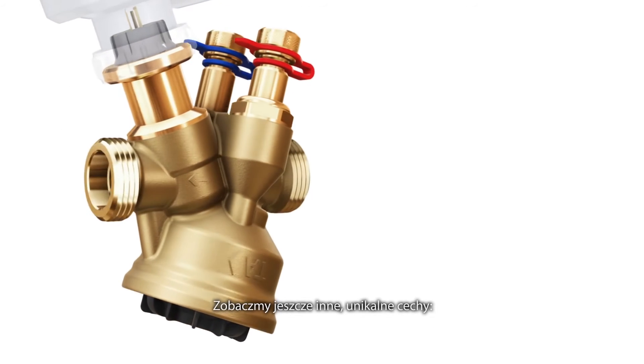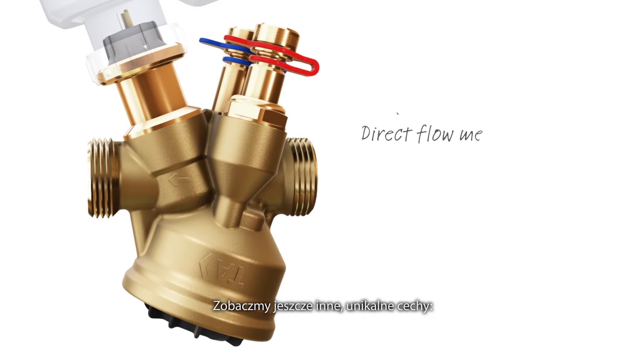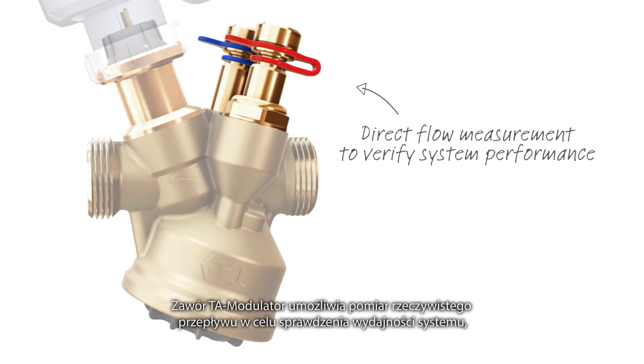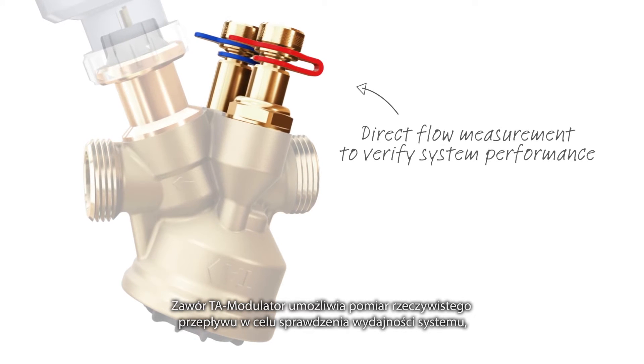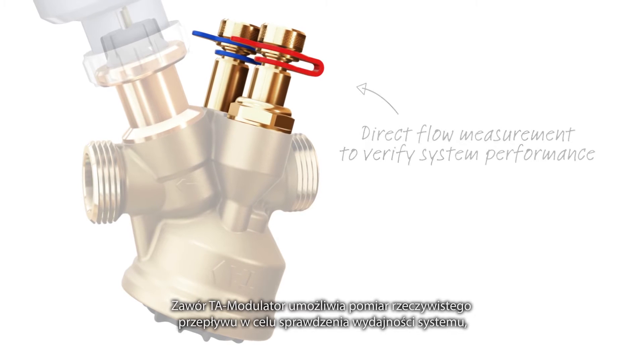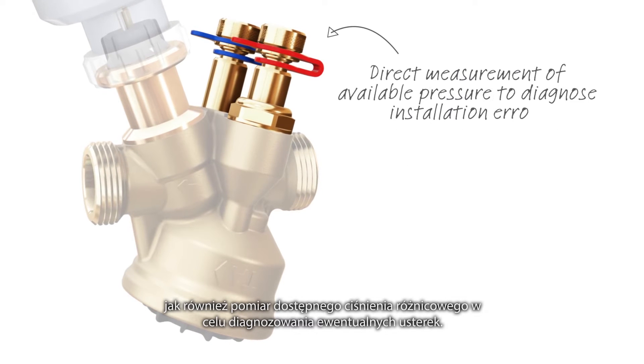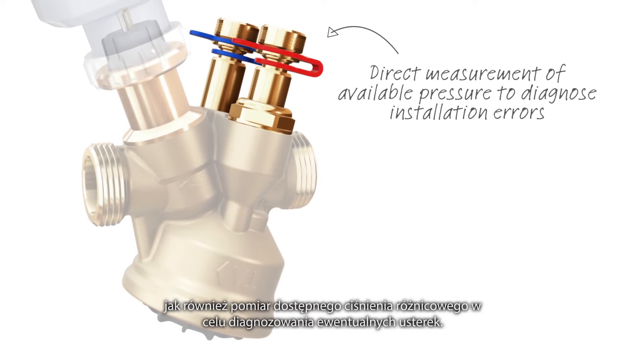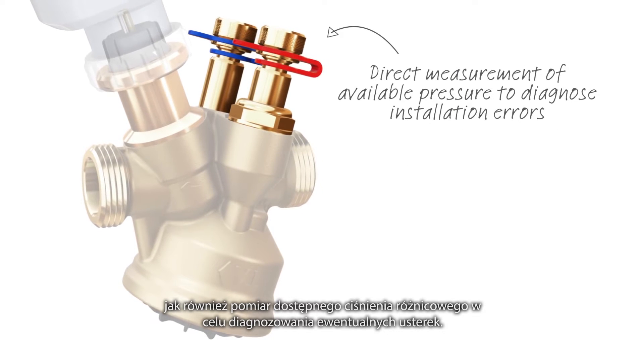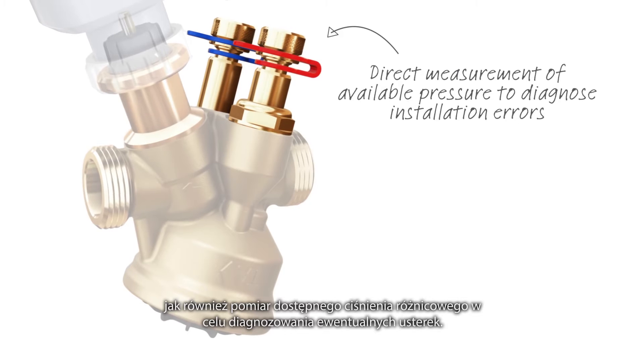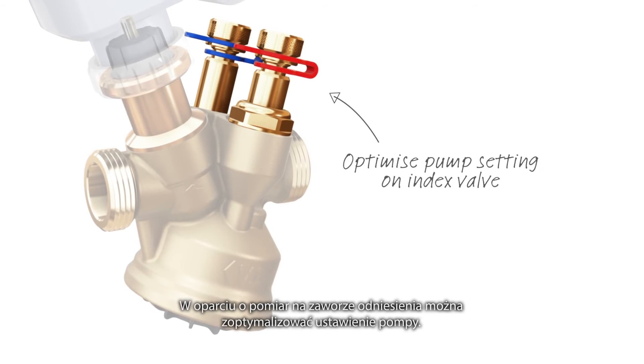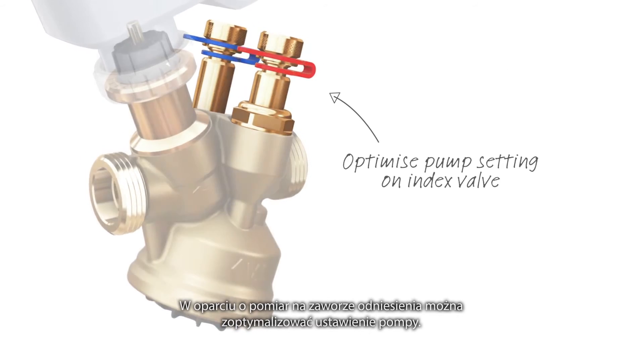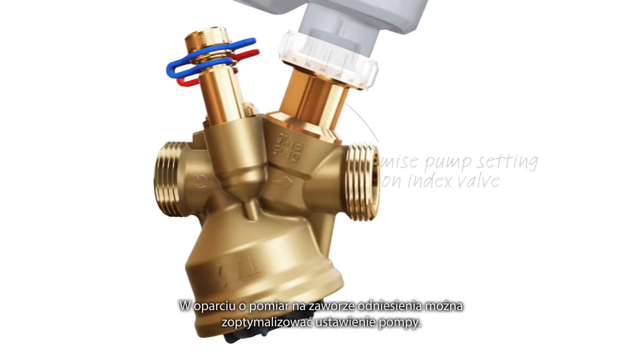With TA Modulator, you can measure the true flow through the valve to verify the system performance, as well as measure the available differential pressure to diagnose possible installation errors. On the index valve, you can optimize pump setting.